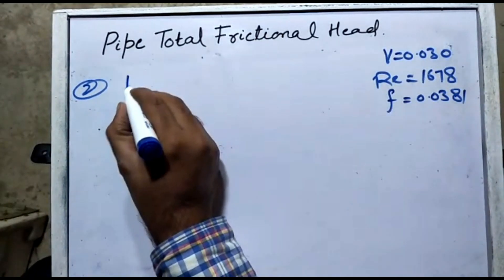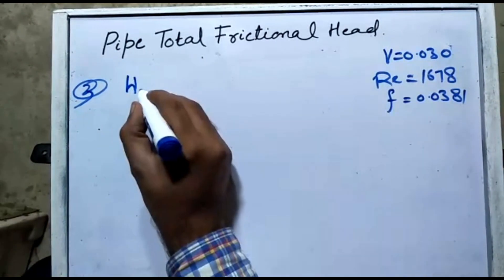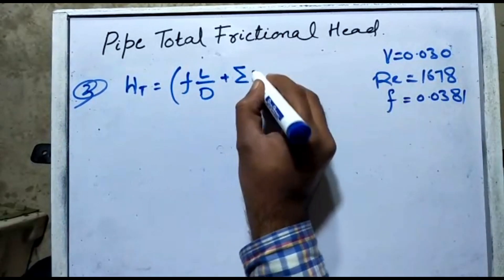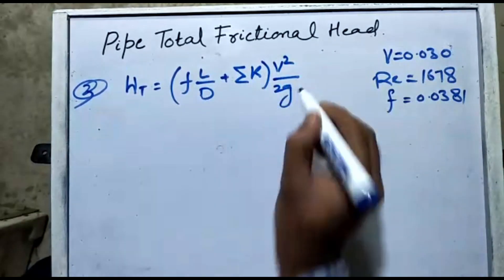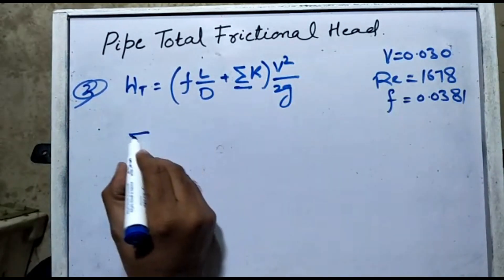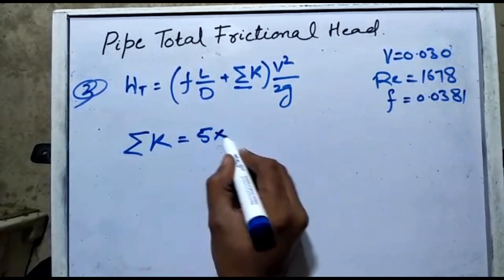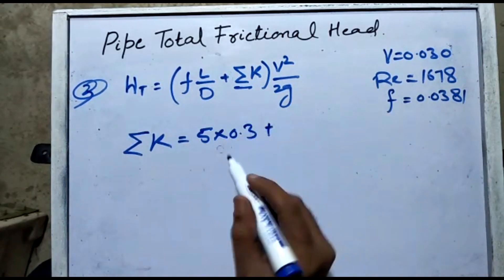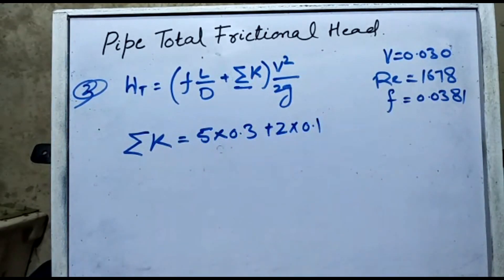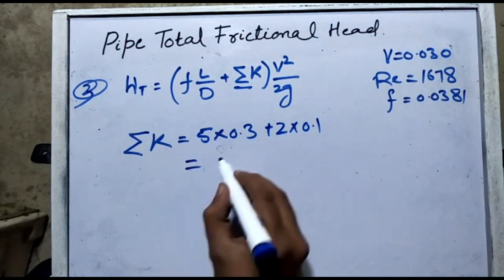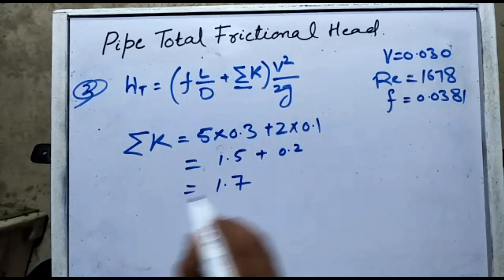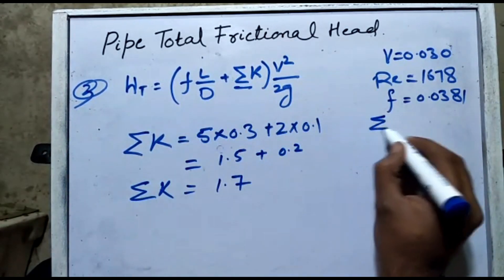Now applying the Darcy-Weisbach equation to find the total head loss: h_f = (f·L/d + ΣK) × v²/2g. First we find the sum of K-values: 5 elbows × 0.3 = 1.5, plus 2 gate valves × 0.1 = 0.2, giving ΣK = 1.7.